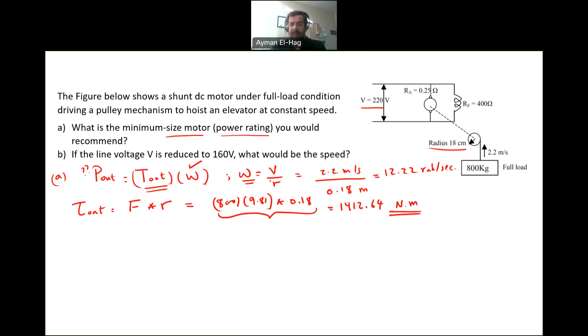Now, from this torque, we can find the output power. So P out is equal to this torque, which is 1412.64 times the omega, 12.22, and this will give me 17,265.6 watt. When you want to size your motor, or you want to buy a motor that can do this load, then this is the size of the motor that you are looking for.